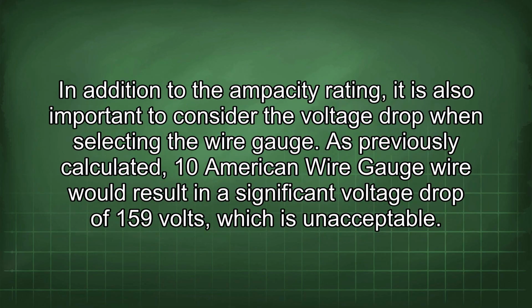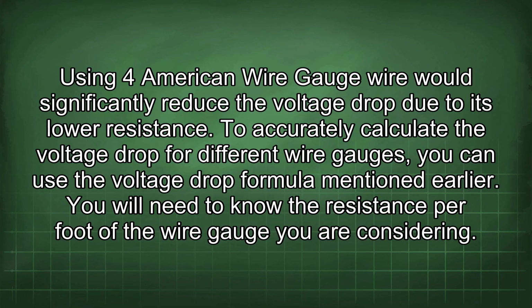In addition to the ampacity rating, it is also important to consider the voltage drop when selecting the wire gauge. As previously calculated, 10 American wire gauge wire would result in a significant voltage drop of 159 volts, which is unacceptable. Using 4 American wire gauge wire would significantly reduce the voltage drop due to its lower resistance.